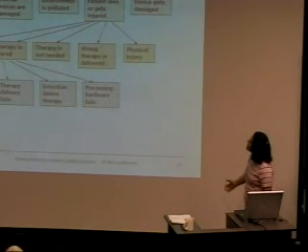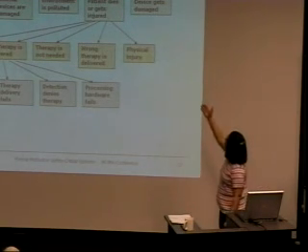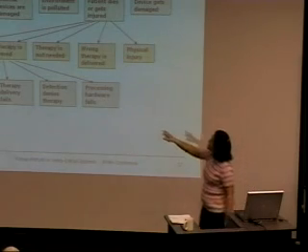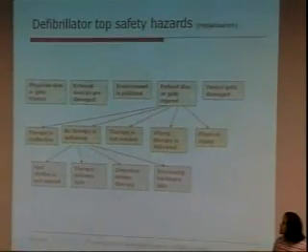So these are the top safety hazards of the defibrillator. For the patient dying fault, there are several reasons, several faults, and for the specific one I chose, I showed these four may happen, and the case of no energy or no shock delivered when the patient needs it. So I won't go into the details of all these faults.